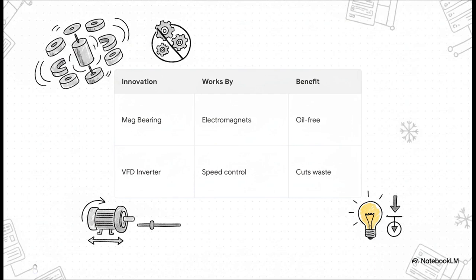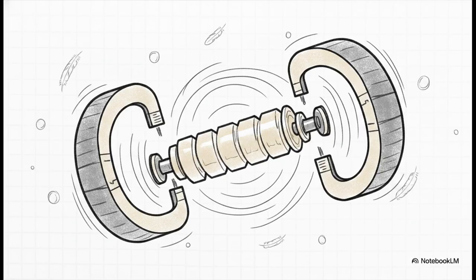First, magnetic bearings. Instead of oil, they use electromagnets to literally levitate the rotating shaft in midair. This makes the system 100% oil-free, eliminating friction completely and maximizing efficiency. Second, the VFD, or variable frequency drive. Old compressors wasted huge amounts of energy running at a fixed speed, like 60 Hz. VFDs provide real-time motor speed control, slowing the motor down to cut power waste at night or during the winter when cooling demand drops.